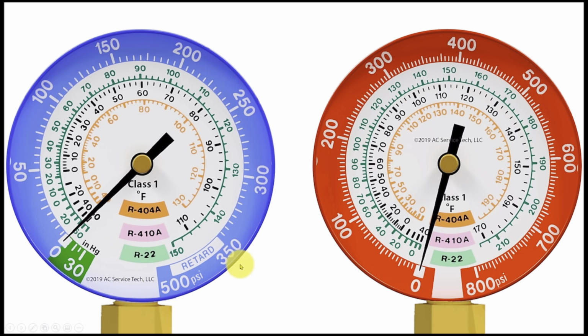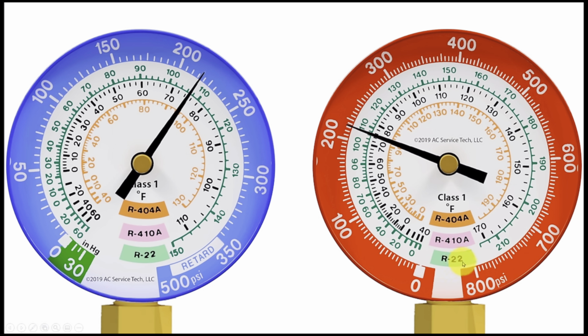The way they work is the outside numbers are the PSI. This blue gauge only goes up to 350, while the red gauge goes all the way to 800. So the blue gauge is the low side, red gauge is the high side. The gauges used in this example are for 3 refrigerants, R22, 410A, and 404A. We're mainly going to focus on the 410A section of where these needles end up.